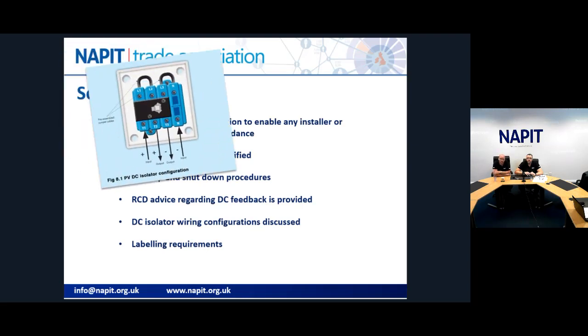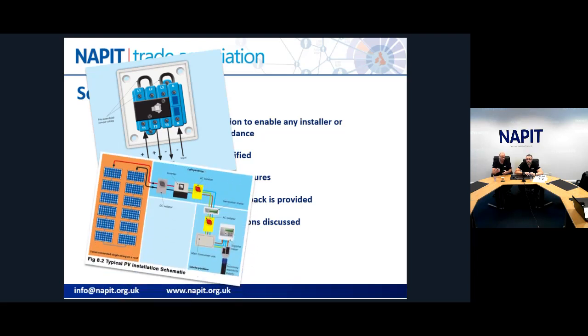For example, this is a typical DC isolator. You can see the positive goes in, across one pole, then through a pre-assembled jumper cable and back up through another pole, so the arc is quenched over two poles, not just one. There are various configurations for different systems and isolators, but this is just a typical example.